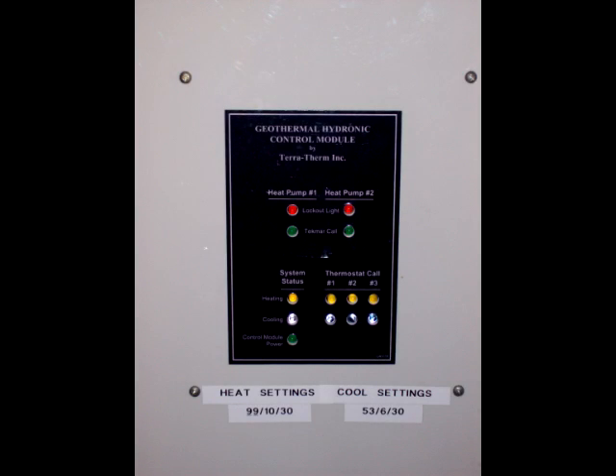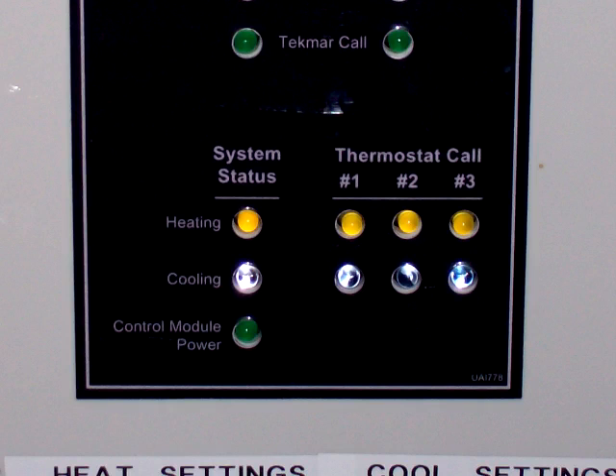As you see, there are a number of LED indicator lights on the front door of the hydronic control module that allow you to see what the hydronic system is doing at a glance. On the lower left side is the green power light, indicating that the control module has power. The next row of lights are the blue cooling indicators. The first light indicates that the system is in the cooling mode. The next 3 lights let you know what zones, 1, 2, or 3, have a thermostat call for cooling. The next row of lights are amber heating indicators. The first light indicates that the system is in the heating mode. The next 3 lights let you know which zones, 1, 2, or 3, have a thermostat call for heating.